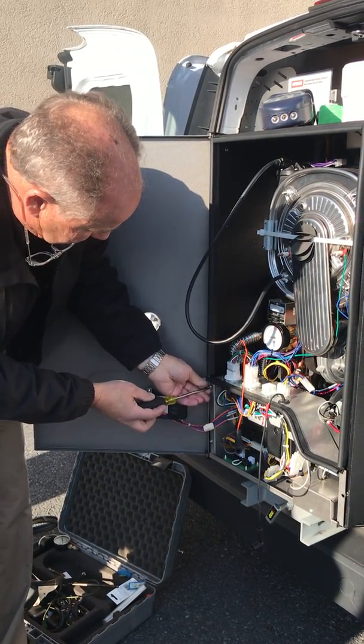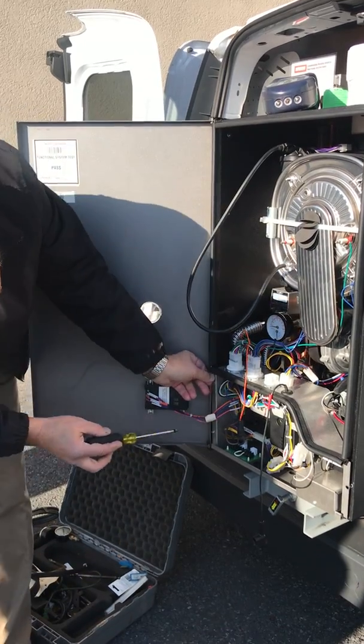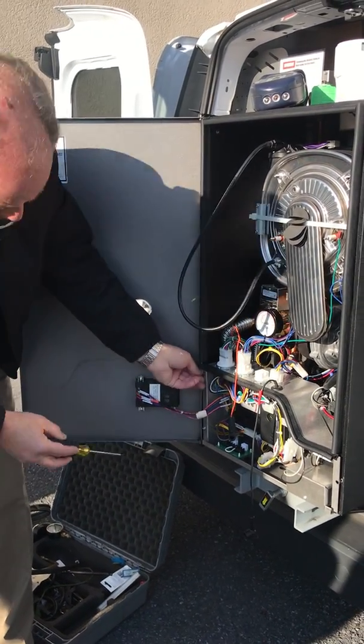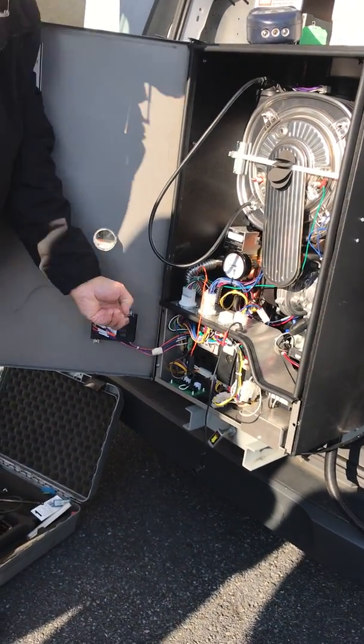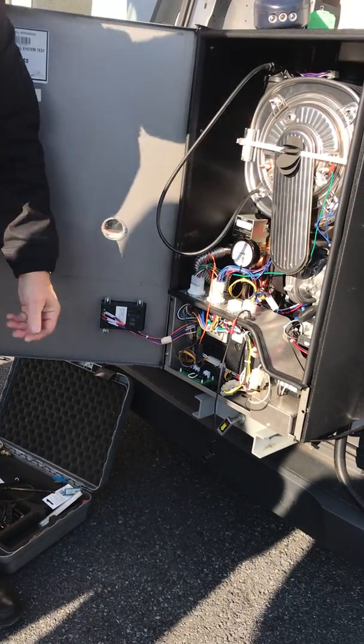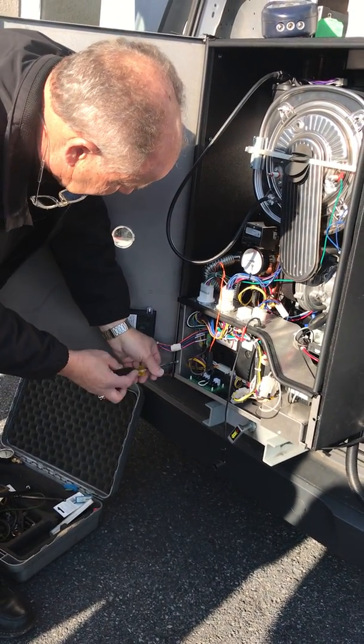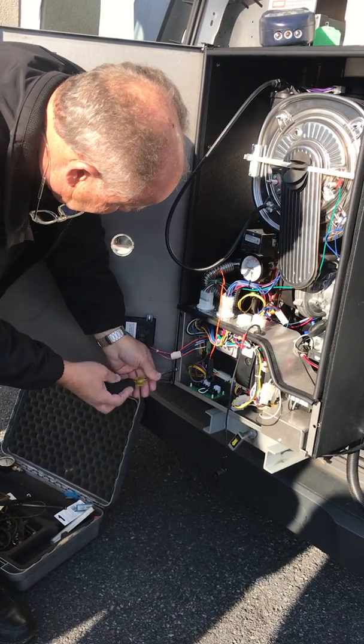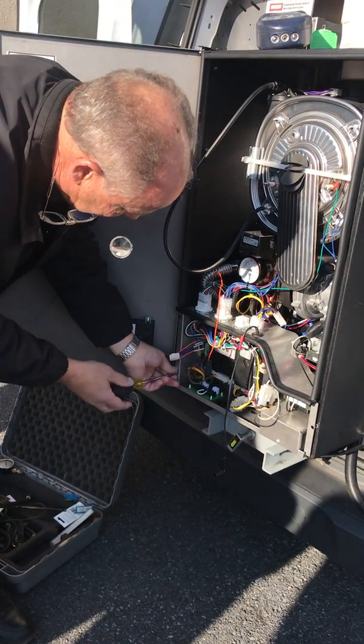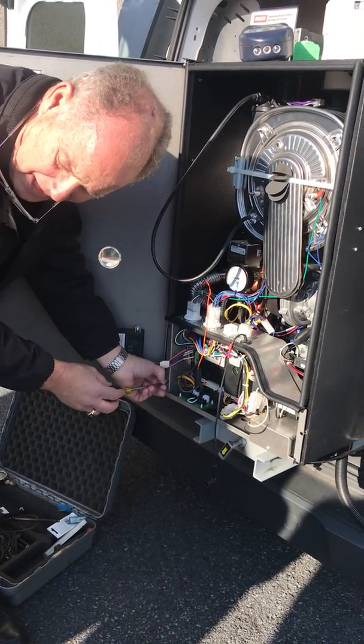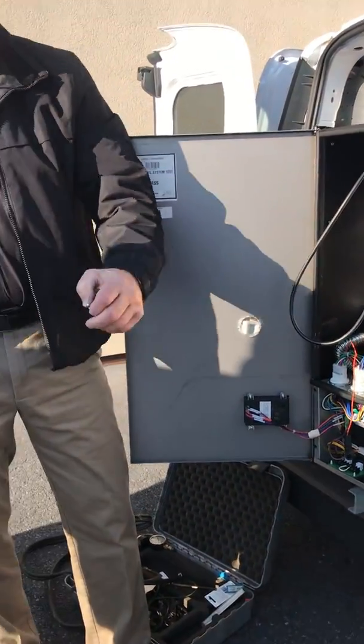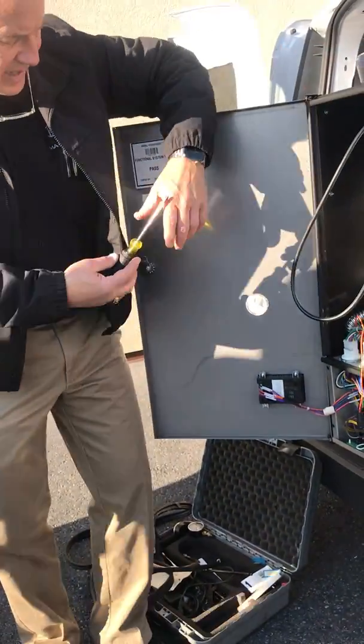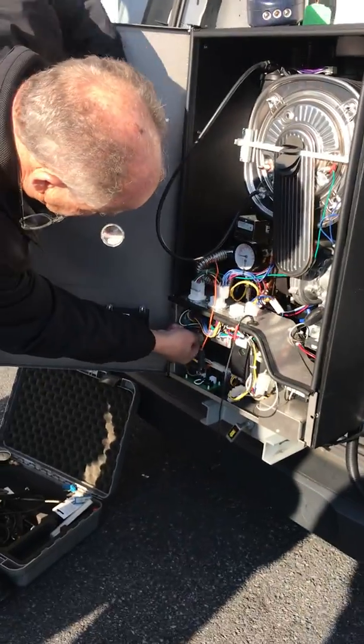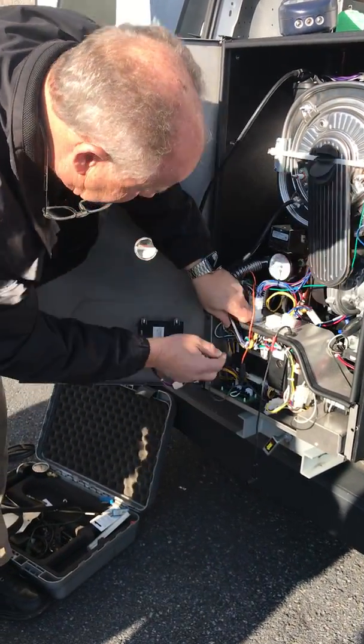What I like about the control is it actually has a green power light on it. The green power light tells me my transformer's working, so I know I got 120 to it. The second thing is that it tells me if I'm on lockout, there's an alarm light. So it lets me know that the boiler's locked out. And the other thing that it has, and this pulls off my display, so I can actually pull that out.